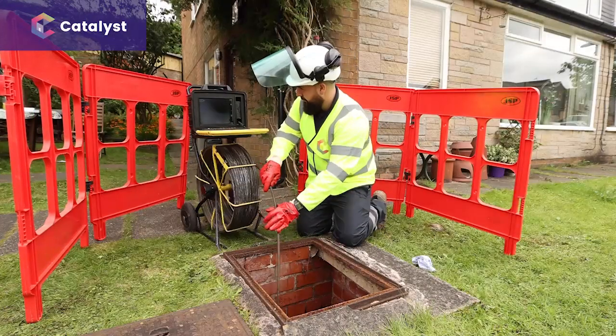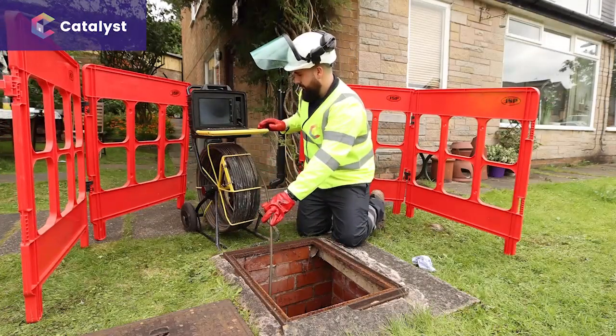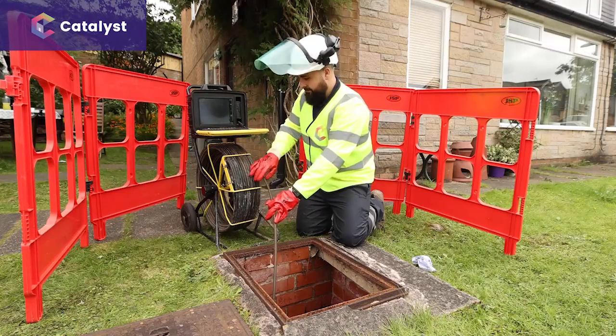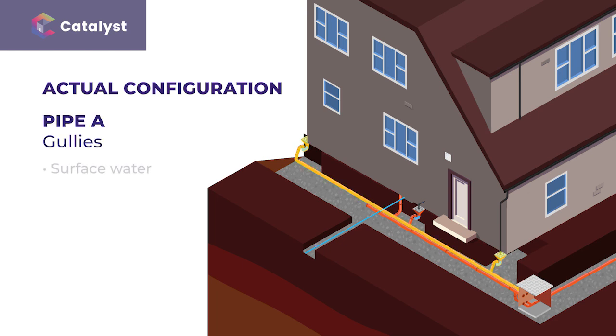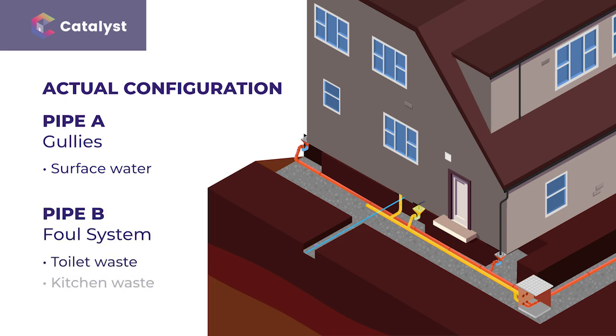Now the pipework is jetted clean, the engineer can start the camera survey. At this point, this property threw up a bit of a surprise. It was found the pipe connections were actually quite unconventional. Unusually, the two surface water gullies were connected to one service pipe, while the foul system for the toilets and kitchen waste were connected to a separate pipe, with both independently entering the same chamber. Without carrying out a drain survey, this unusual configuration would not have been easily identified.